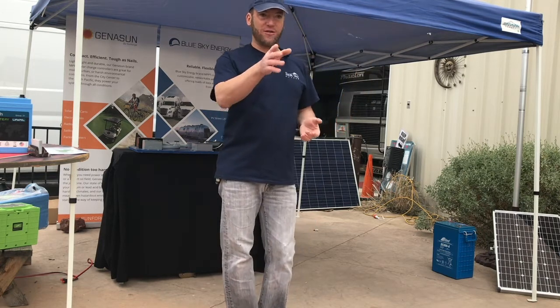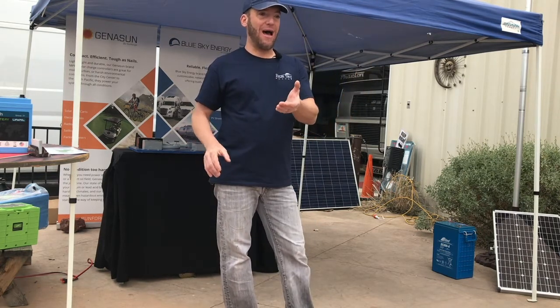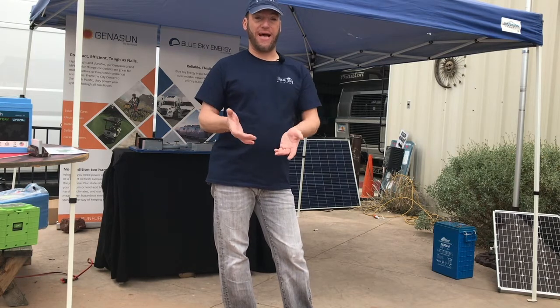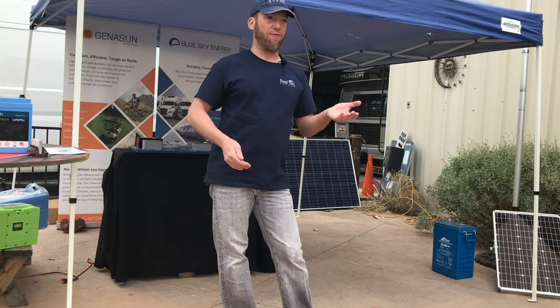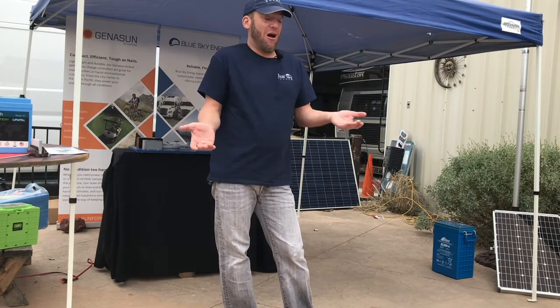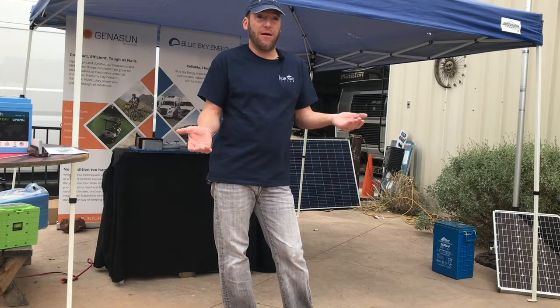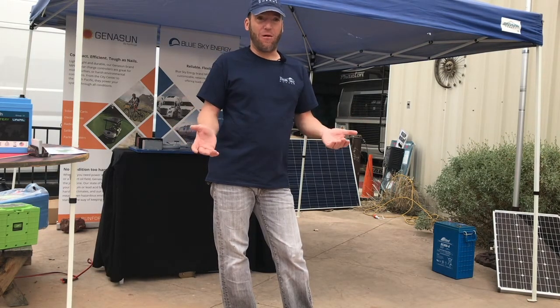You can do what you're saying, and there's a lot of translation. For example, a lead acid battery, if you set it to 14.4 absorption and 13.6 float, that's not a horrible charge profile. It might be a little high on the float, but it's not horrible.